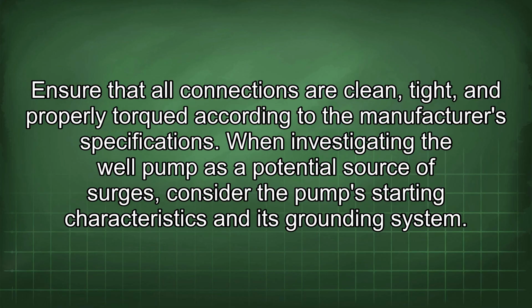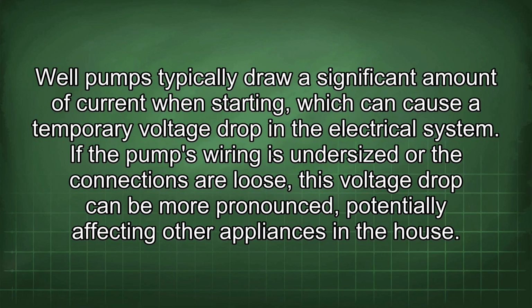When investigating the well pump as a potential source of surges, consider the pump starting characteristics and its grounding system. Well pumps typically draw a significant amount of current when starting, which can cause a temporary voltage drop in the electrical system. If the pump's wiring is undersized or the connections are loose, this voltage drop can be more pronounced, potentially affecting other appliances in the house.